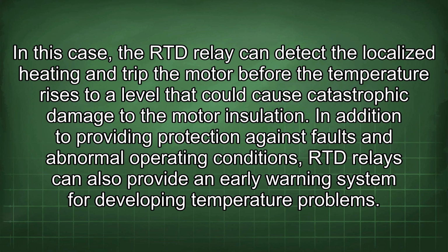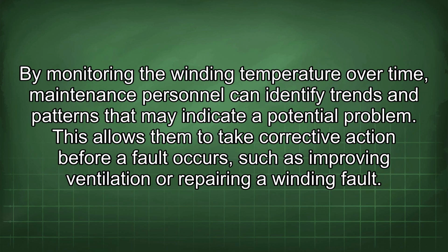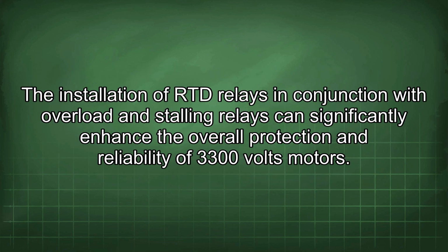In addition to providing protection against faults and abnormal operating conditions, RTD relays can also provide an early warning system for developing temperature problems. By monitoring the winding temperature over time, maintenance personnel can identify trends and patterns that may indicate a potential problem. This allows them to take corrective action before a fault occurs, such as improving ventilation or repairing a winding fault. The installation of RTD relays in conjunction with overload and stalling relays can significantly enhance the overall protection and reliability of 3300 volts motors.